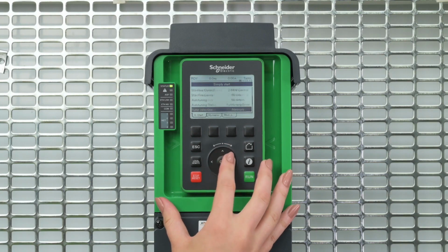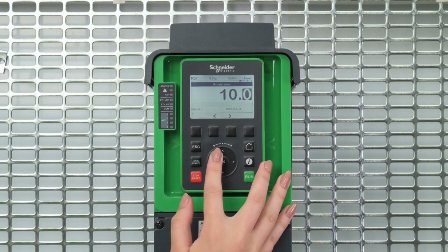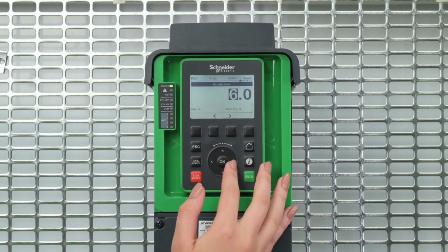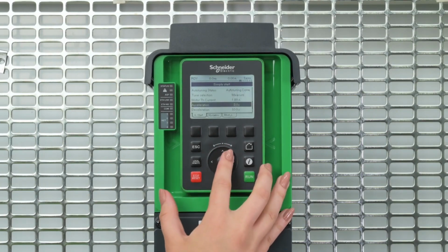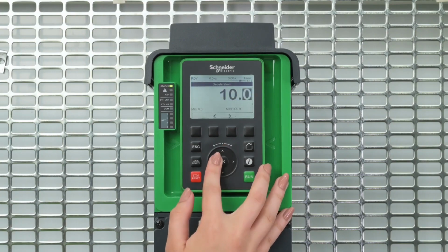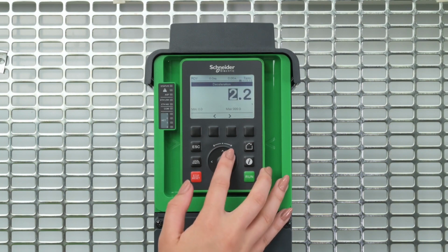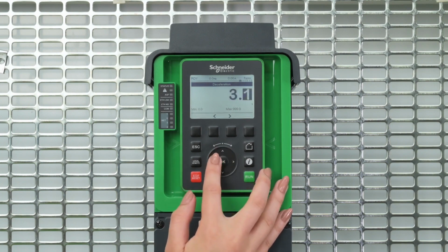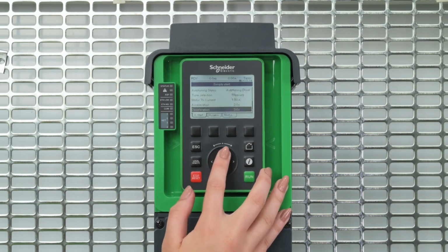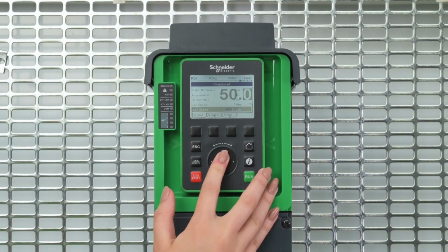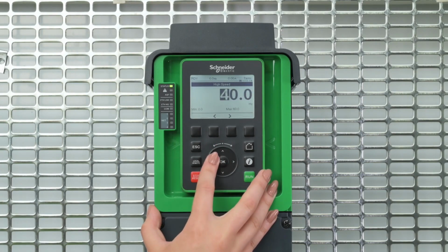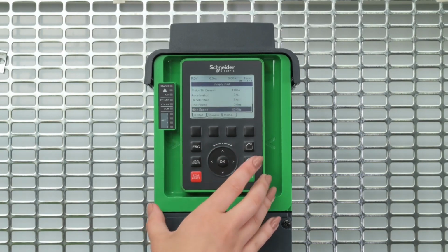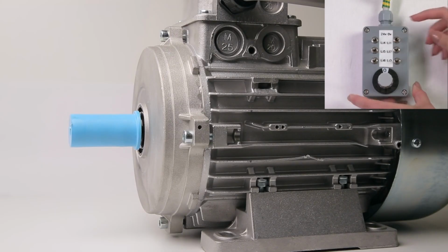The last operation to perform is setting the drive according to the application requirements. In this example, an acceleration time of 3 seconds, a deceleration time of 3 seconds. And a high speed limited to 40 Hz. You can now start your motor.